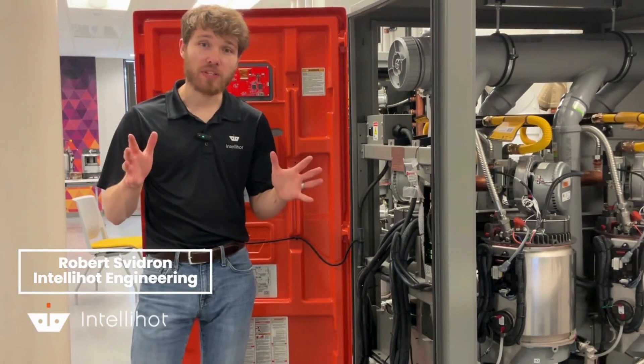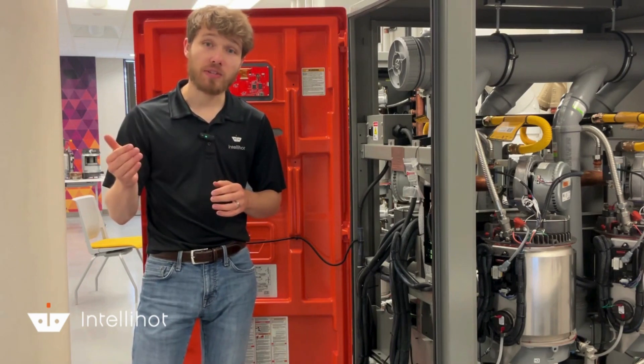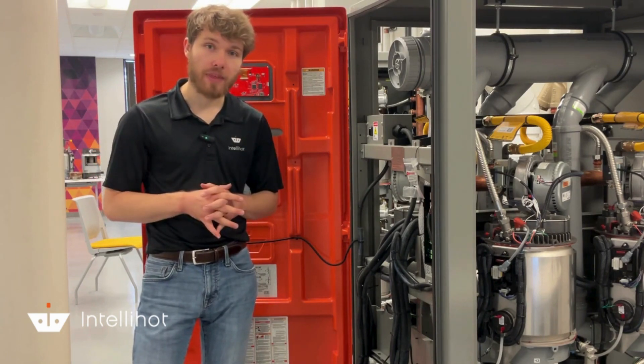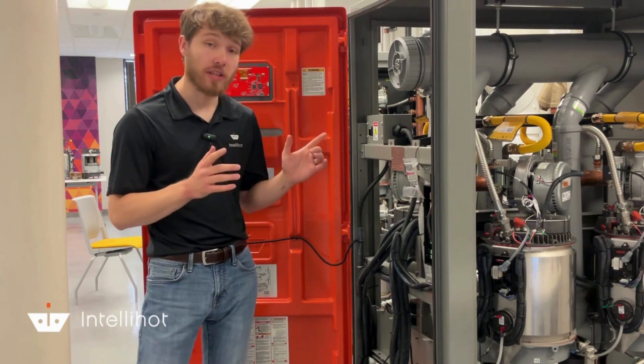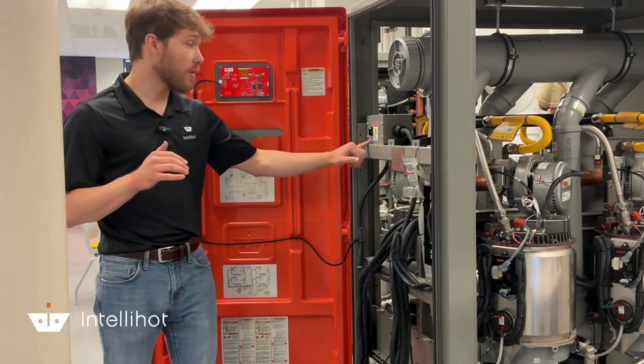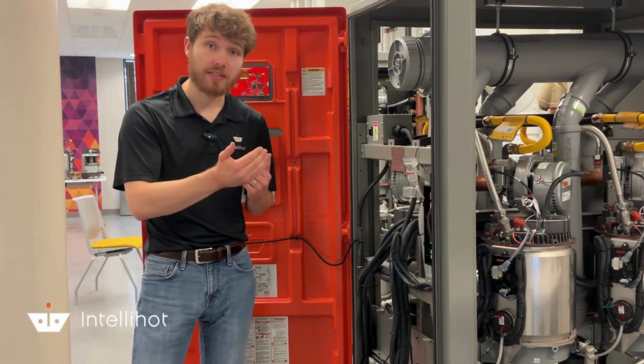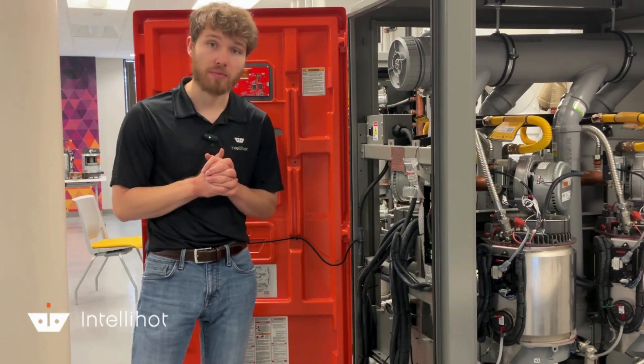Hey guys, today we're going to be replacing a blower on an IQ 1001 unit. We're going to be using our new SPR8 Revision 1 blower and we're replacing an Ametek. First thing before we start the blower replacement, I want to make sure that my unit is powered off — I want to make sure I'm doing that at the rocker switch. I also want to make sure that the gas is isolated to the unit. You don't want any gas on during the replacement process.